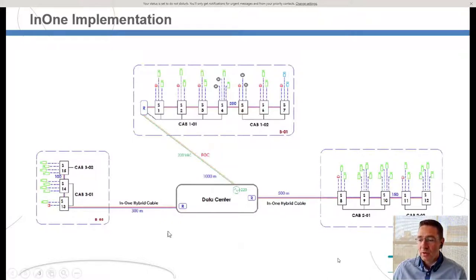From here, we go with hybrid cable all the way to the cabinets, feeding them DC power directly. As Jawad mentioned, there's a power board termination where we terminate fiber and power within the cabinet and provide regulated 48 volts to the switches inside. Even from cabinet one to cabinet two, it goes through hybrid cable, the same for all the blocks.